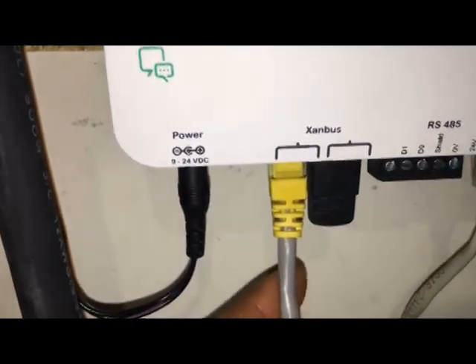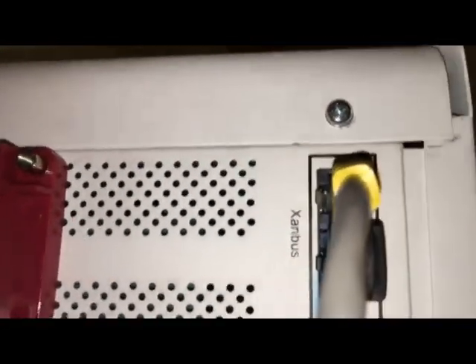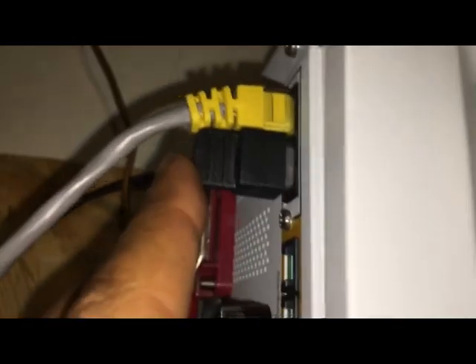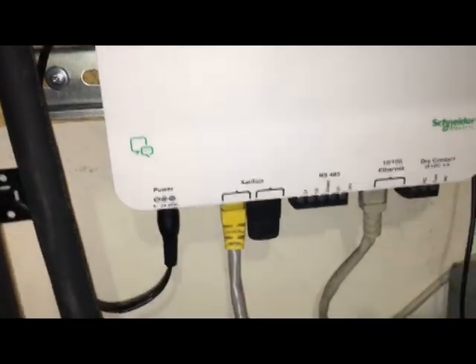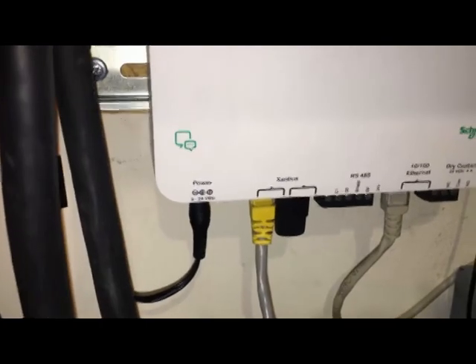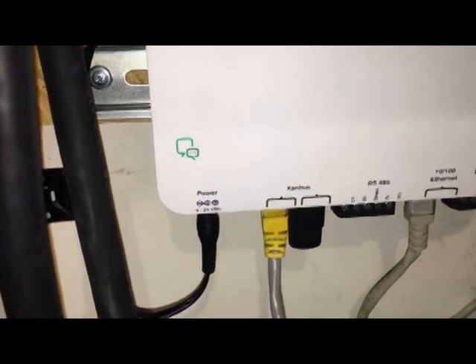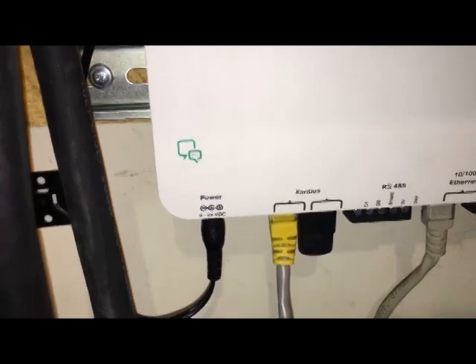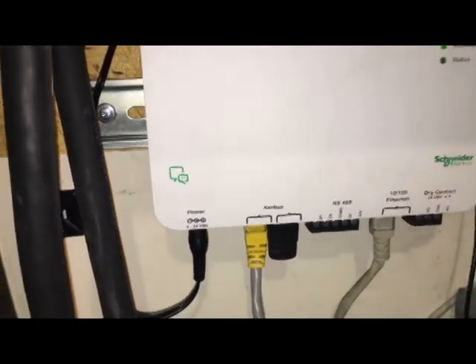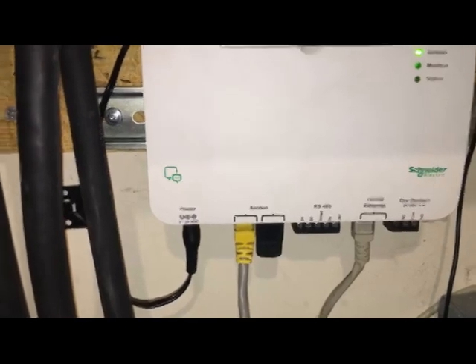This is a standard network cable, basically a Cat5 Ethernet cable, that connects to the Xanbus connection on the inverter charger. The thing on the side here is a network termination plug on both sides, which closes the loop between Xanbus devices. This is again a proprietary network connection that allows the unit to talk to, configure, and control other units.